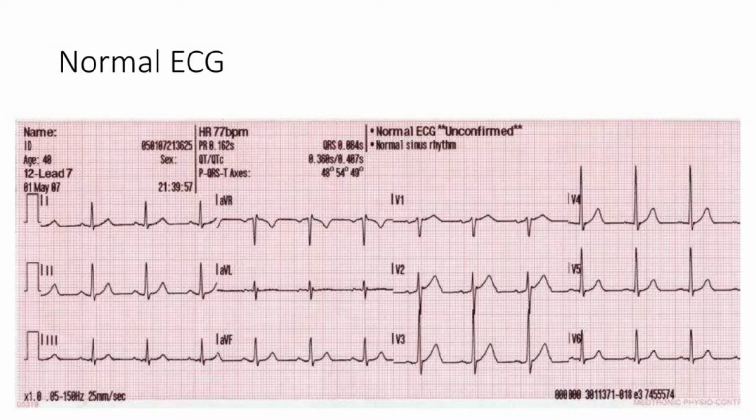This is very important, especially for filtering out respiratory movement. Respiratory movement can give you an undulating baseline, and so the presence of this filter filters out these low frequency waves in order to give you a clean baseline. Same thing with the high frequency, the low pass filter, which is 150 hertz there, which means that frequencies below that will be allowed through, and frequencies above that, like myopotentials, muscle twitching, and AC current, will be filtered out in order to give you a smooth baseline.